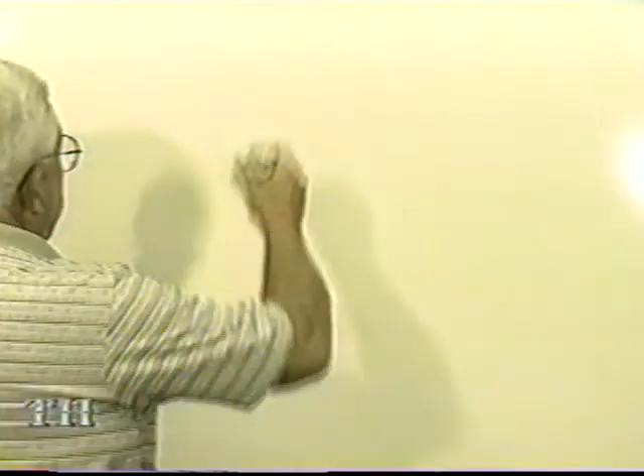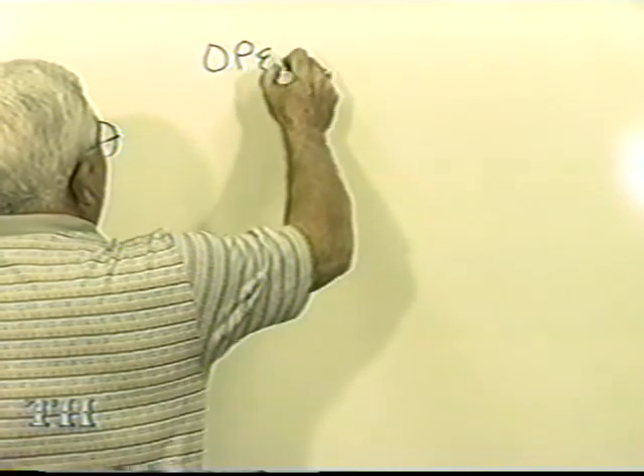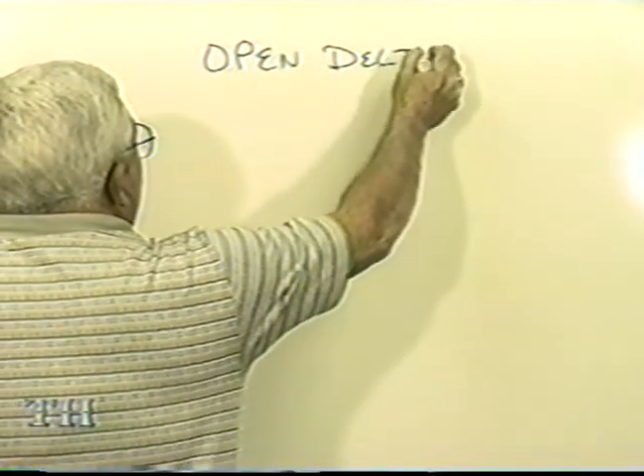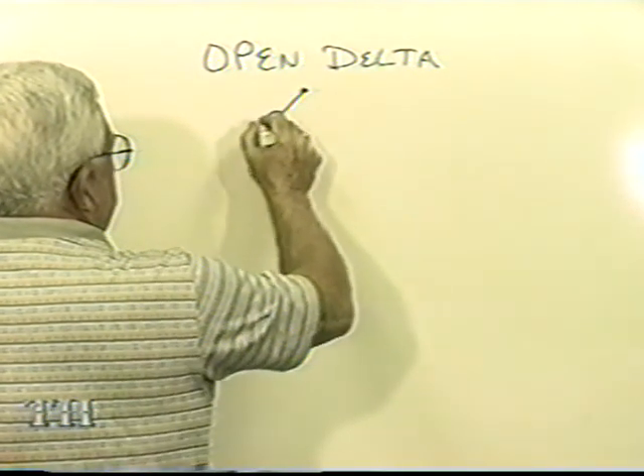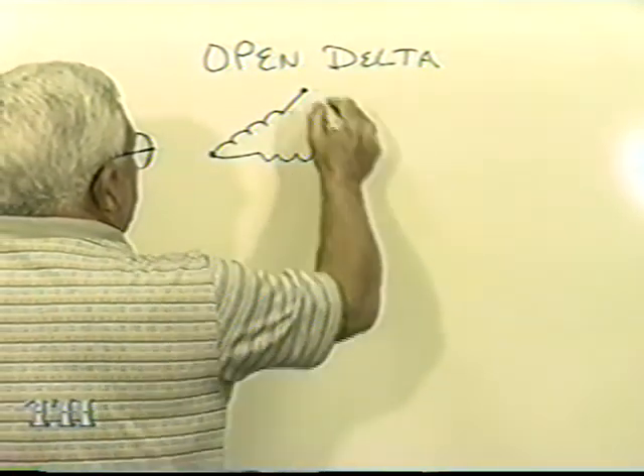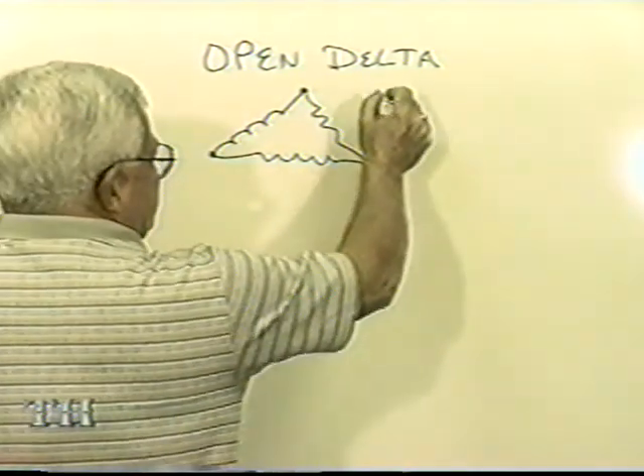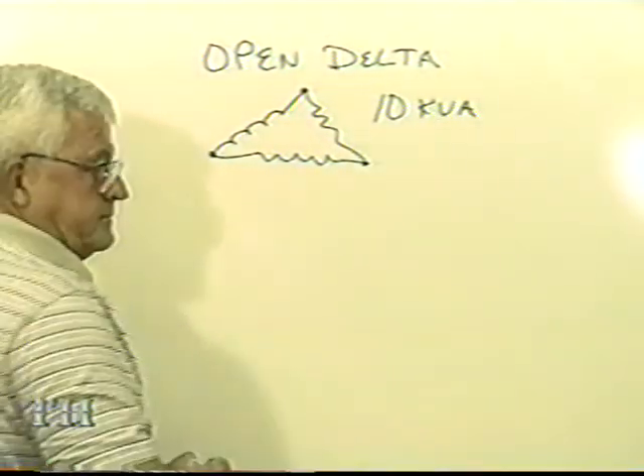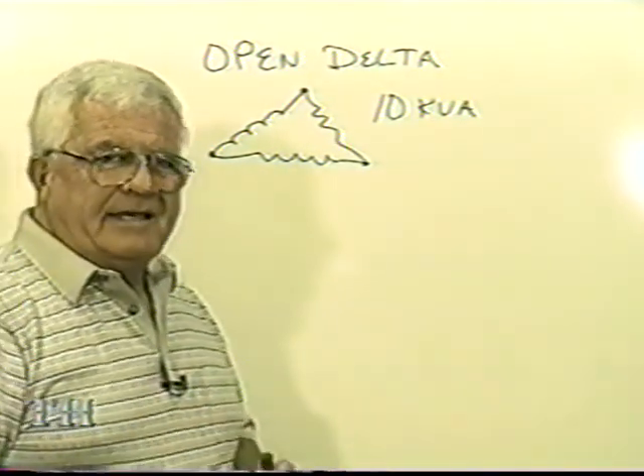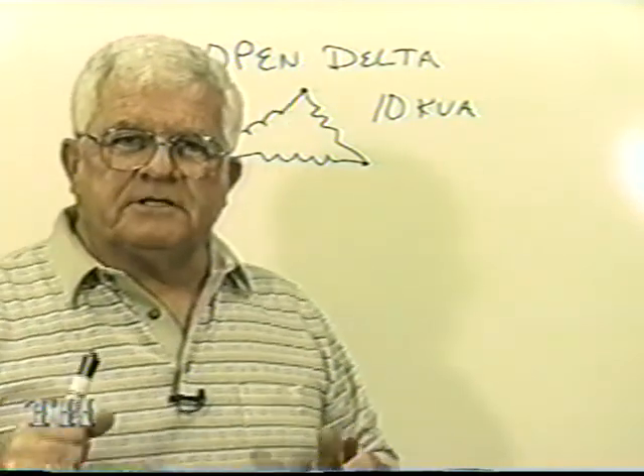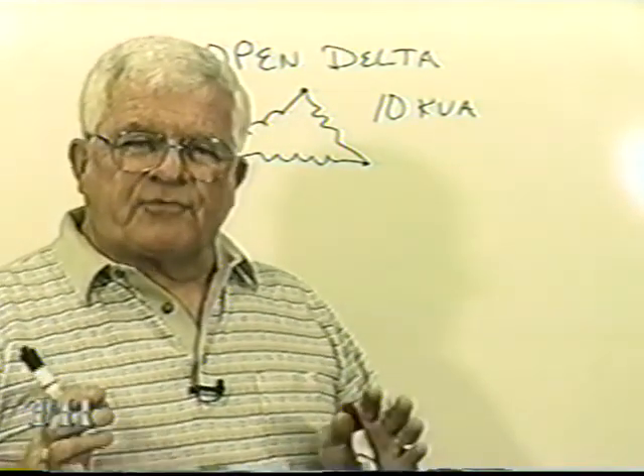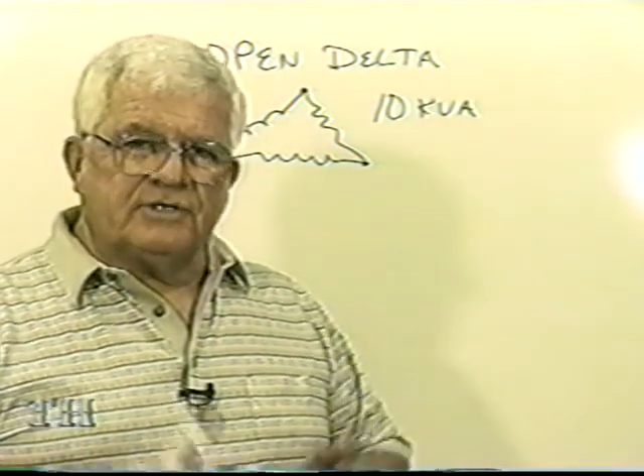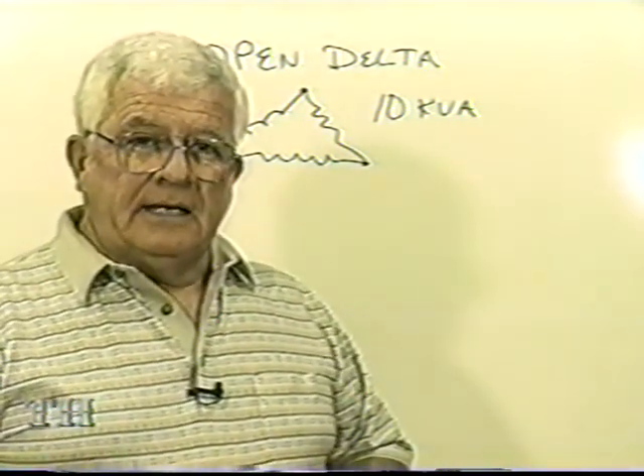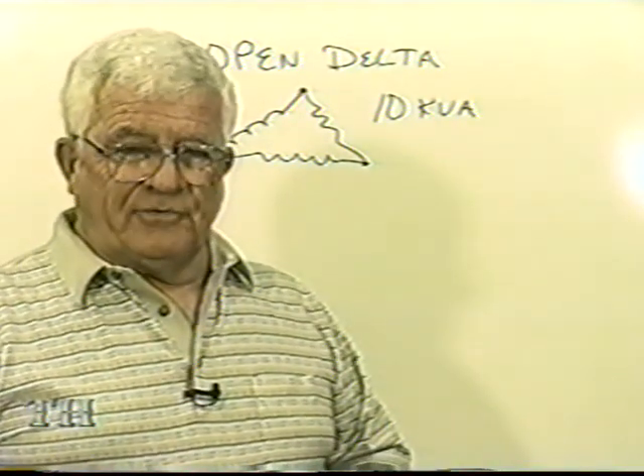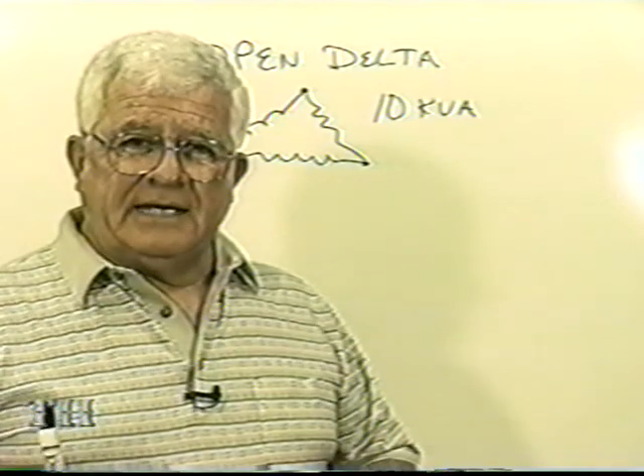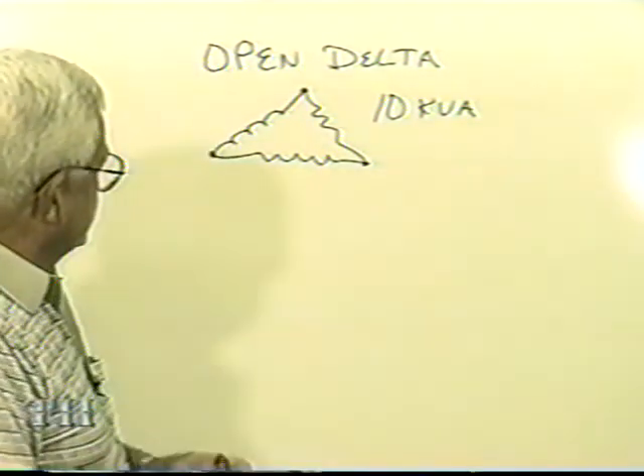Now I'm going to talk about open delta. Say we had this delta transformer, and let's say it's 10 kVA, just to have numbers. It's kind of like the old phrase, you put all your eggs in one basket. So you can take 3 coils and put them all in one transformer, or you can set 3 single transformers. In the industry, it's best to set 3 single transformers, that way if one would burn out, if I would lose one of these, watch.